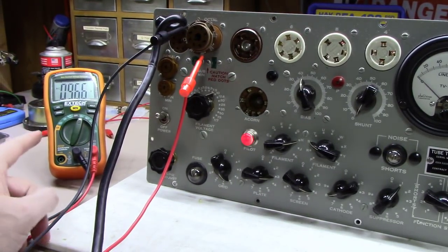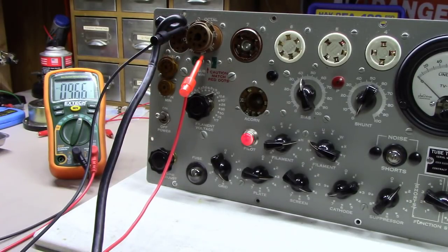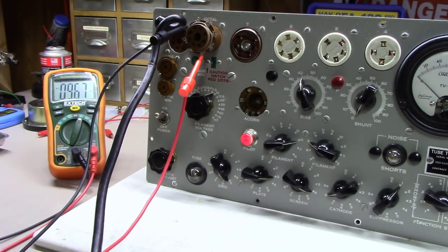And if you'll notice, I'm at 9.66 volts across 2 and 7, and I've let the unit warm up now for 15 minutes or so. And if you remember, this should be at 10.03 to 10.12. So we've now got to adjust R134 until that is actually true.